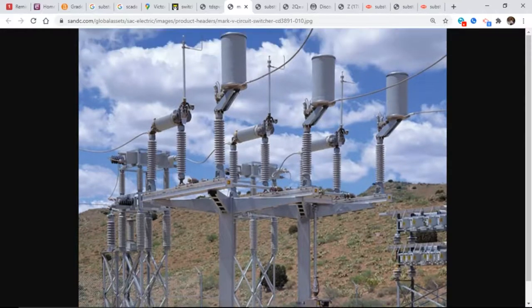All right, you'll notice on the ACI here, this one is open. How can I tell? It's straight up and down. When closed, this arm lays into this connection right here. You see these jaws that are right here. It just falls straight down in and lays in these jaw connections right here. Even though this is the electrical connection, all right, you'll see these three components right here. One, two, three. And in this tube, notice and understand, the conductor comes in here, goes through this insulated tube, and then to the bar, all right?